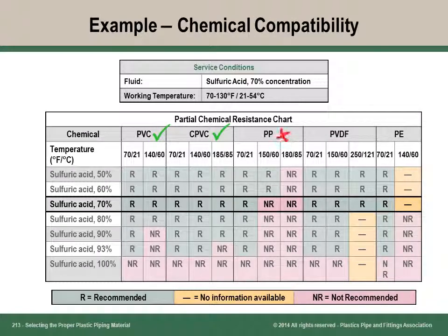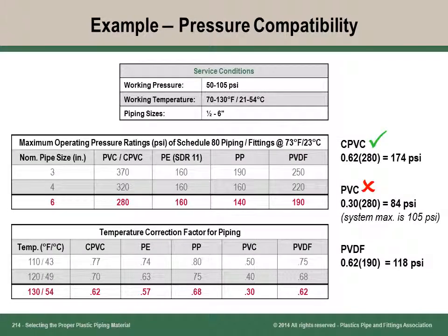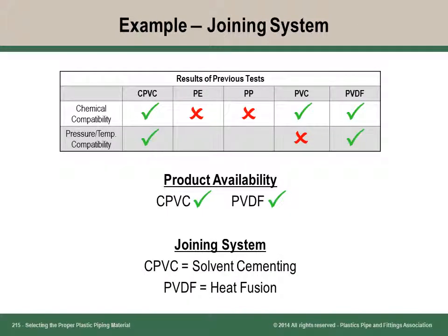Chemical resistance is first checked to settle on which plastic piping material, if any, can handle the designated fluid. However, be aware that many solutions are mixtures and all fluid components must be considered. The next step is to decide the ability of the plastic piping products to handle the pressure and temperature that is expected. Steps number 3 and 4 are to find out which piping products are available and to select the most cost-effective joining system.